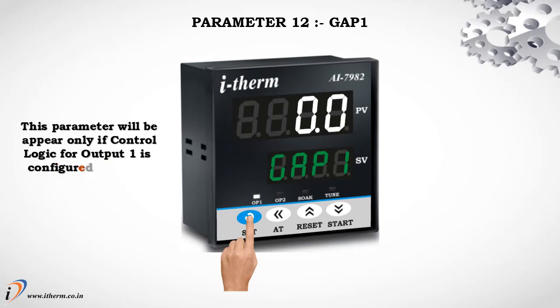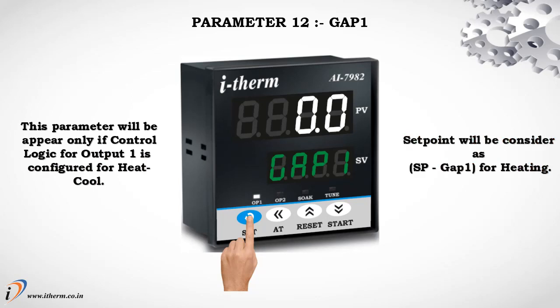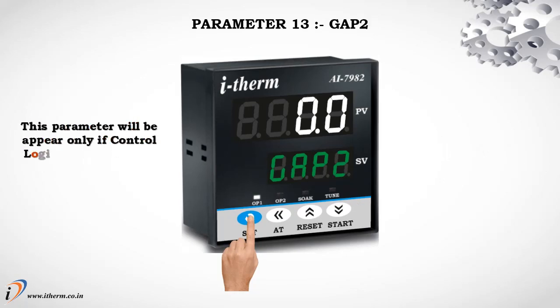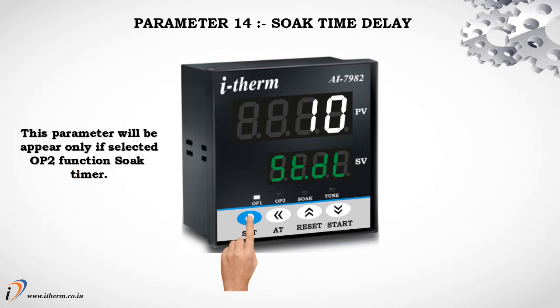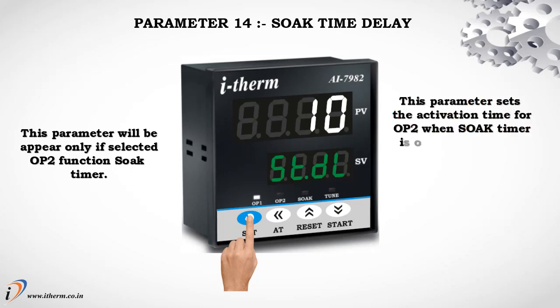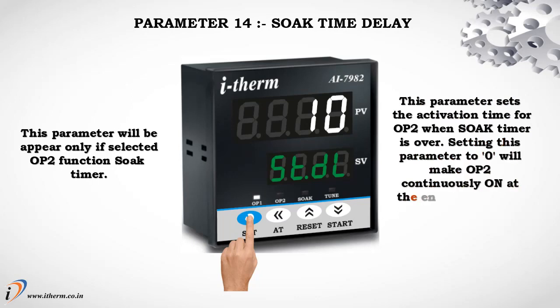Parameter 12: Gap 1. This parameter will appear only if control logic for output 1 is configured for heat-cool. Set point will be considered for heating. Parameter 13: Gap 2. This parameter will appear only if control logic for output 1 is configured for heat-cool. Set point will be considered for cooling. Parameter 14: Soak time delay. This parameter will appear only if selected output 2 function is soak timer. This parameter sets the activation time for output 2 when soak timer is over. Setting this parameter to 0 will make output 2 continuously on at the end of soak time until user starts the next cycle.